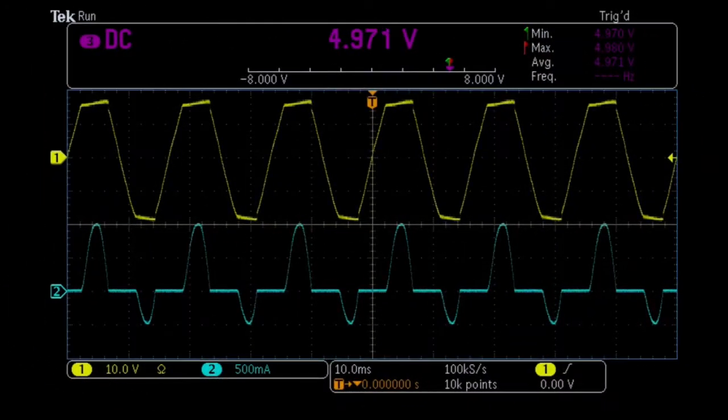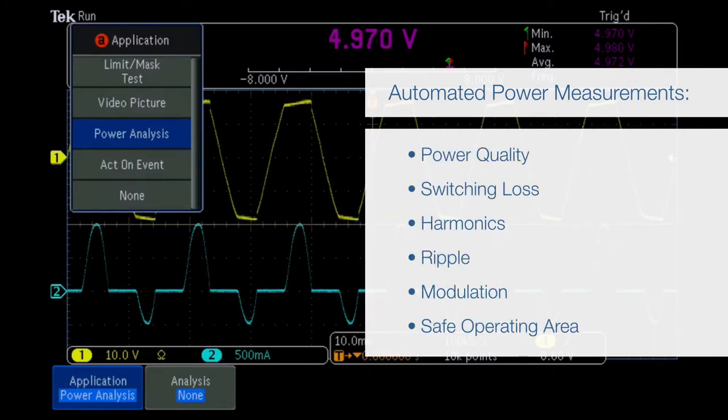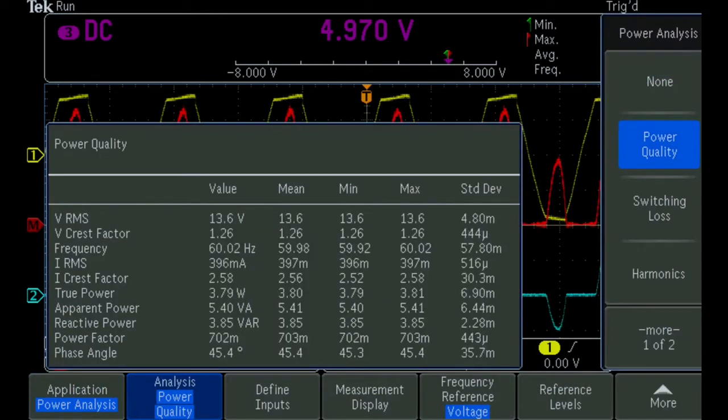The optional MDO3000 power measurement application automatically makes a variety of measurements with the push of a button, easily and repeatably. Here are the input power quality measurements, including power, crest factor, and power factor, which characterize the effects of the power supply on the AC power source.